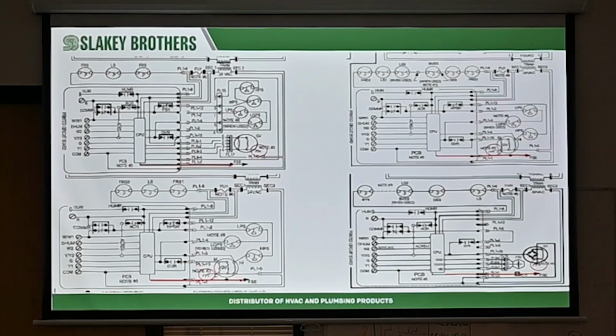The 2-stage gas valves are easy. When you're looking, you got a common, and then you have low stage and high stage. So put your meter on common to low stage, 24 volts. Is it opening up? No. Bad gas valve.